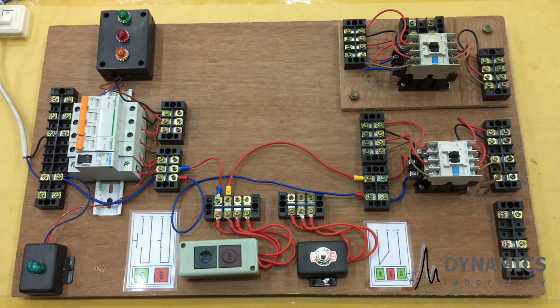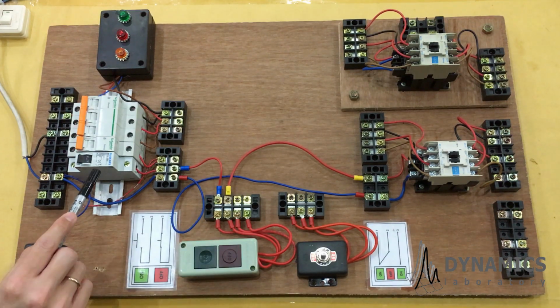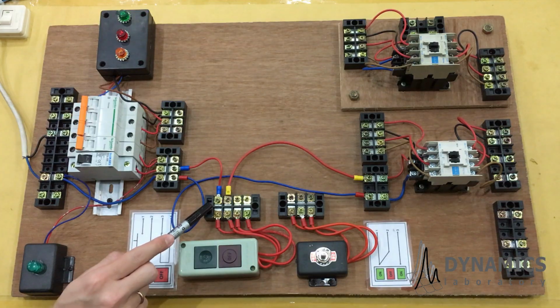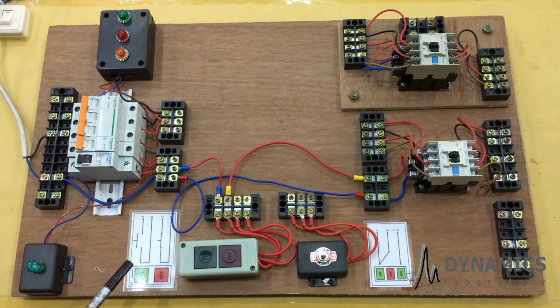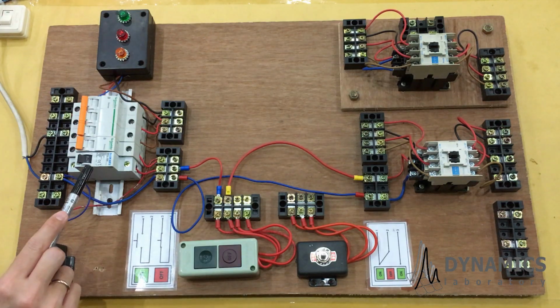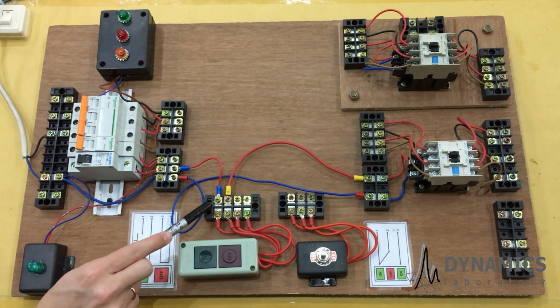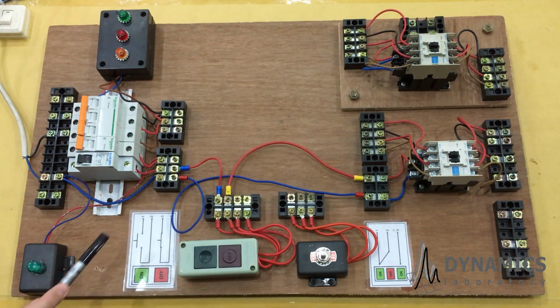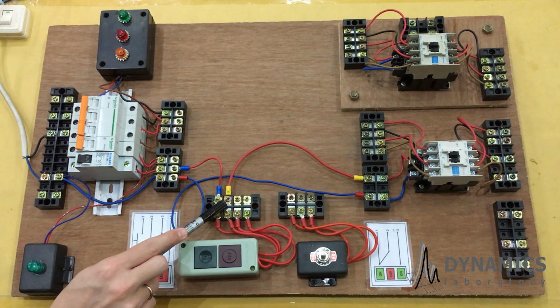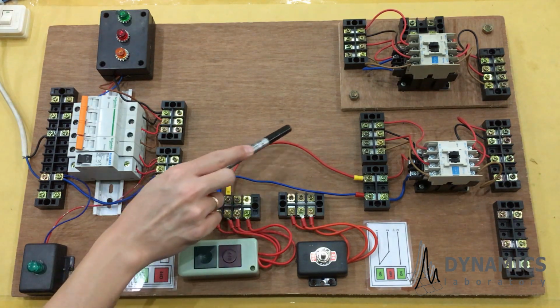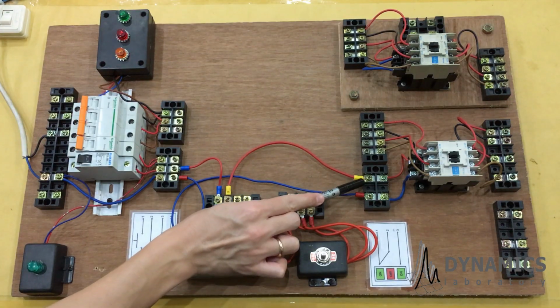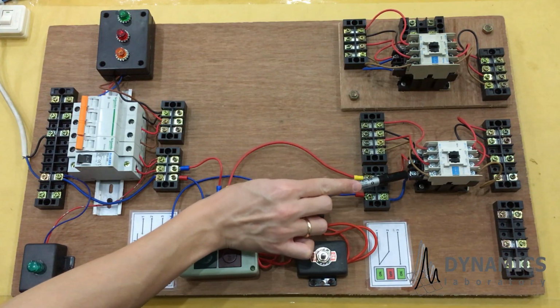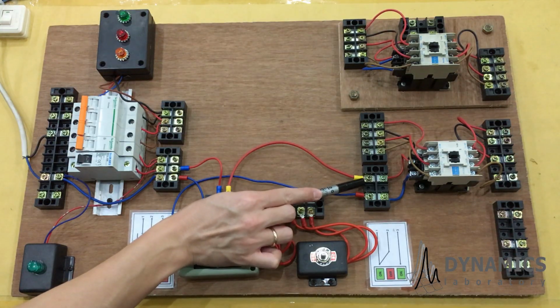Push button. Push button is the simplest control circuit. First, we connect control circuit breaker with push button normally open leg. As you can see in this label, normally open leg of the push button is leg number 1 and leg number 2. That's why from control circuit breaker, I connect it to leg number 1. After that, I connect push button leg number 2 to coil contactor. This is coil contactor, the black one in here, and the terminal of coil contactor is in here.